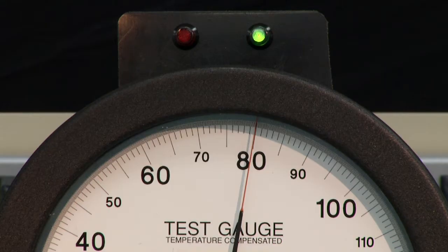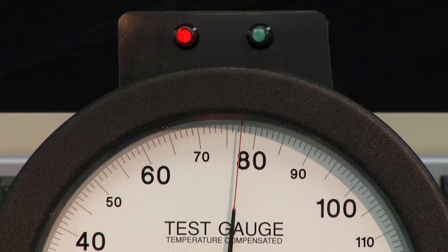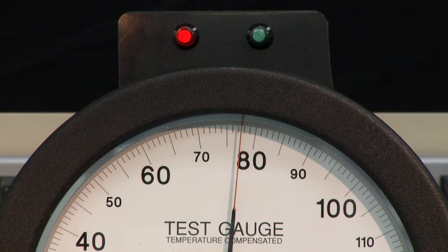In this case, we're virtually on 80. So that's a pretty good set point. And then we will lower the pressure to measure the reset point. And that looks like it's just over 78 PSI. So we have a set point of 80 and a reset point of approximately 78. So we have a dead band of 2.